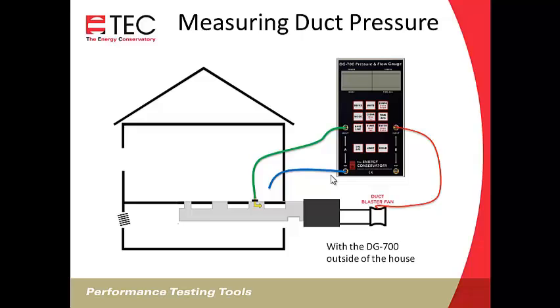What we're measuring, our duct pressure, we're always measuring with reference to the house. Common terms used are either "with respect to" or "with reference to." That's the top tap with reference to the bottom tap, which is the reference tap. So you might see duct/house, or duct WRT, with respect to house. That's the top tap on the gauge with respect to the bottom tap on the gauge, duct to house.